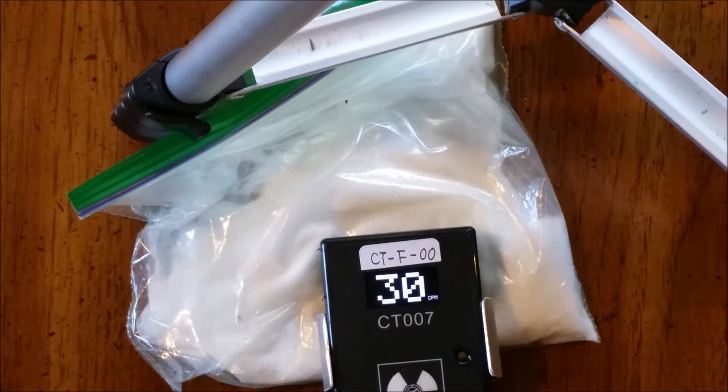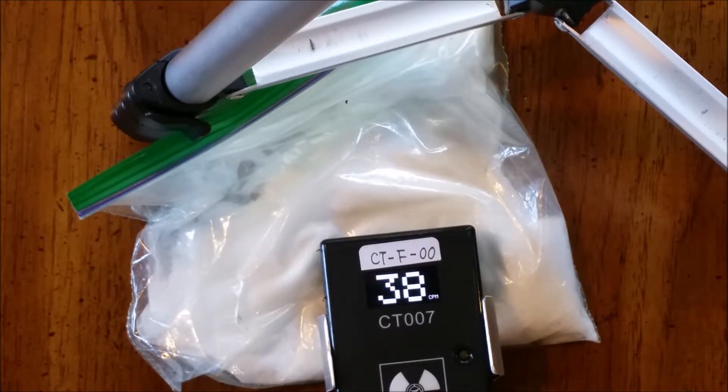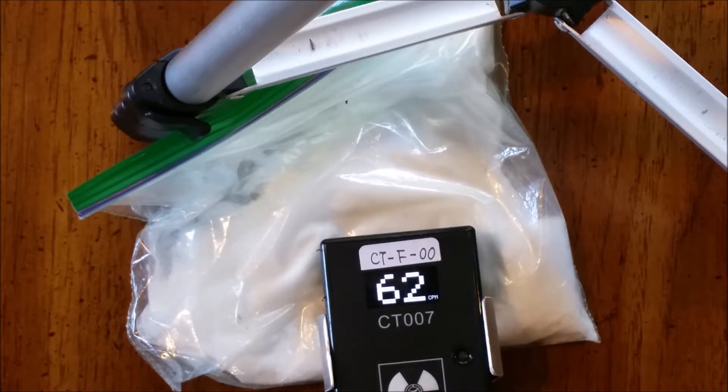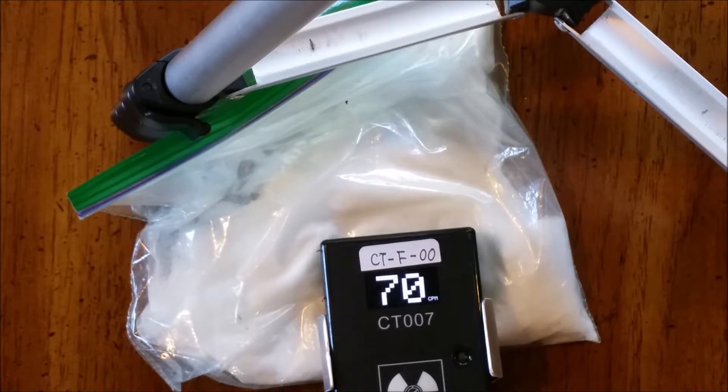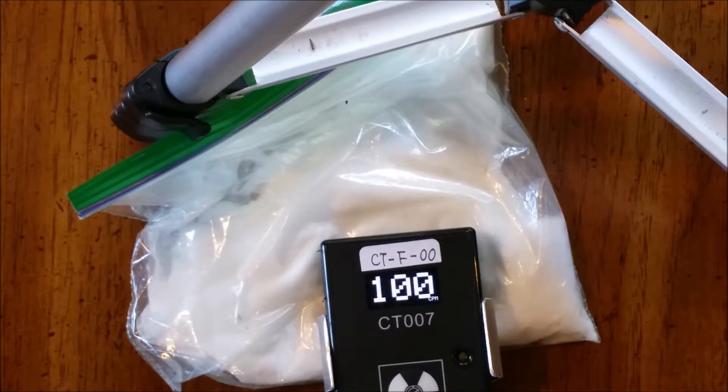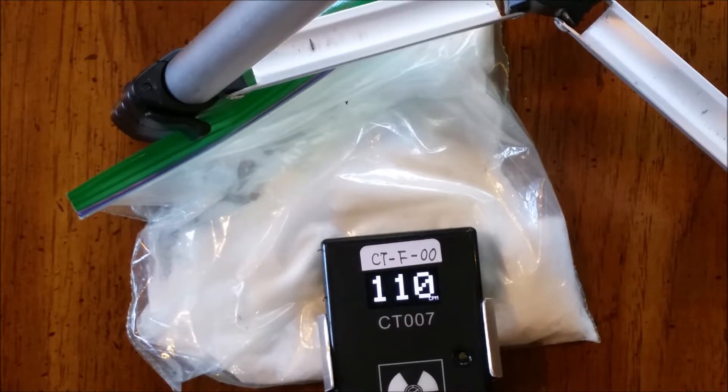This is on a thirty second averaging. The display is averaging the count rates for every thirty seconds. So we'll wait a few seconds for this to reach its maximum. So yeah, the no salt gives us about 100 CPM or about ten times background with the beta window open.